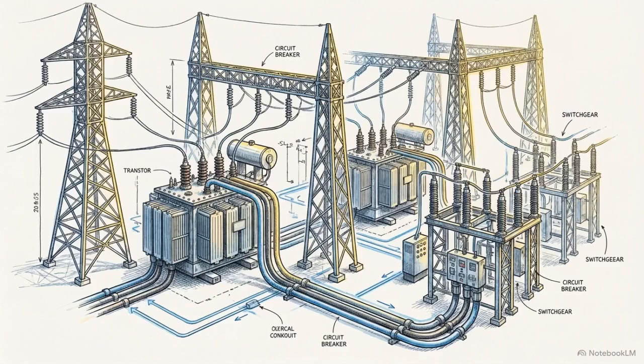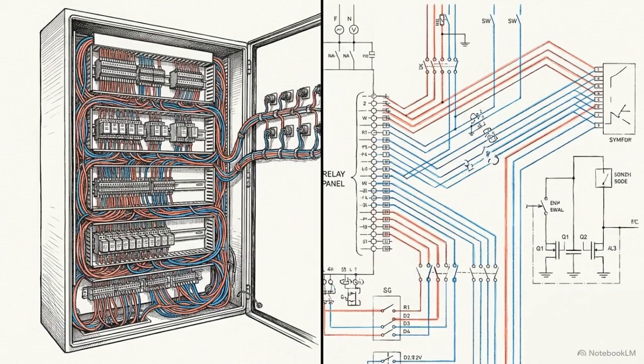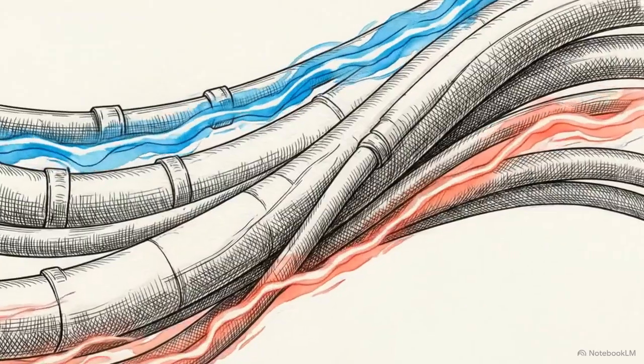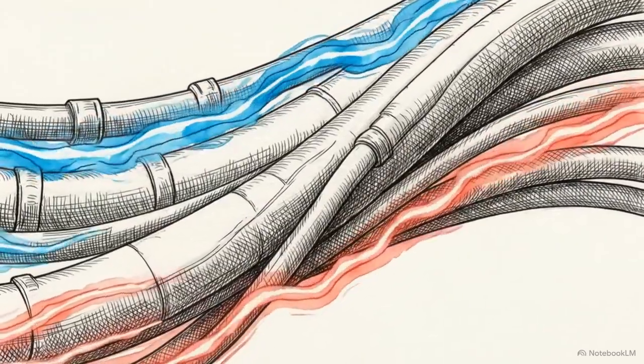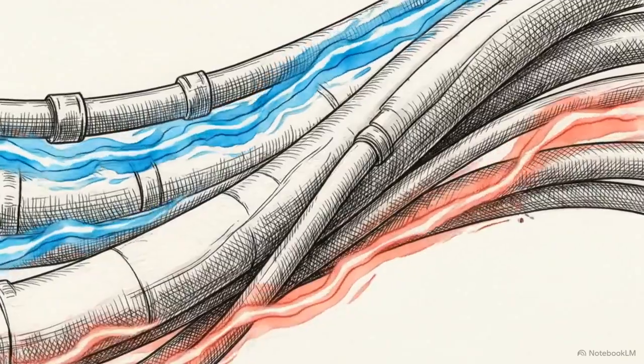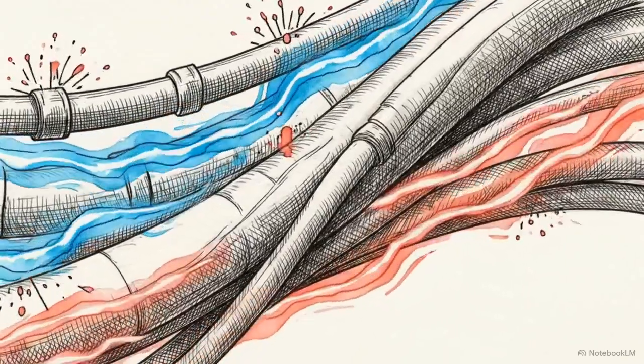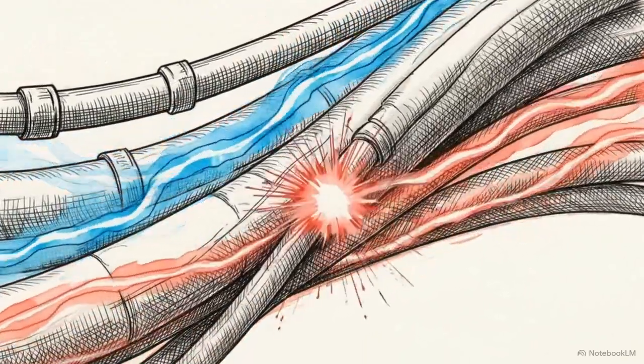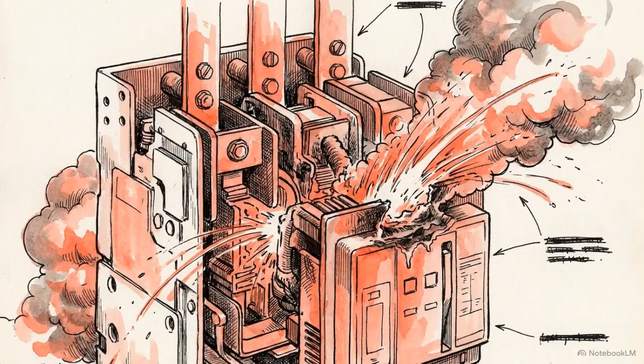Before a single volt flows through a new electrical substation, we must prove one non-negotiable fact. The physical panel wiring and the internal relay logic must be a flawless mirror of the approved engineering schematics. We are preparing to unleash a massive scale of energy into a new installation. The control logic governing that energy must behave exactly as intended, or the consequences of failure are catastrophic.